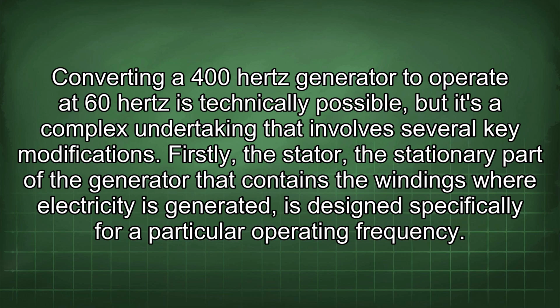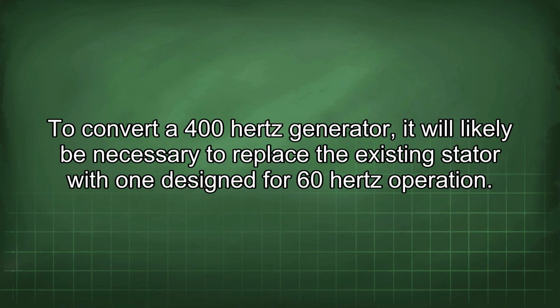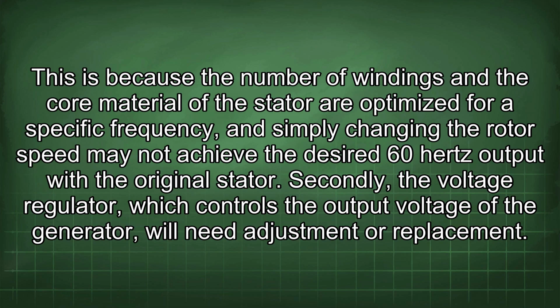Converting a 400 Hz generator to operate at 60 Hz is technically possible, but it's a complex undertaking that involves several key modifications. Firstly, the stator, the stationary part of the generator that contains the windings where electricity is generated, is designed specifically for a particular operating frequency. To convert a 400 Hz generator, it will likely be necessary to replace the existing stator with one designed for 60 Hz operation. This is because the number of windings in the core material of the stator are optimized for a specific frequency, and simply changing the rotor speed may not achieve the desired 60 Hz output with the original stator.